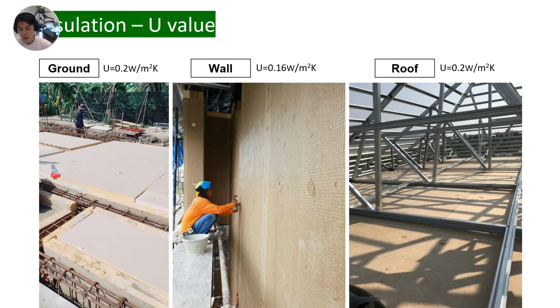Now, some of you may not be familiar with U values, so let me give you a simple idea. In a typical energy-hungry building, the U value is very high. For example, a wall made only of concrete often has a U value of around 3.5 watts per square meter K. That's quite common, but it means a lot of heat is coming through.